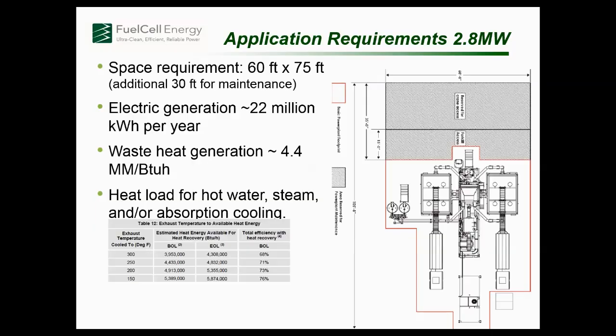For a population of about 400,000, we can put in a 1.4 megawatt fuel cell, and for a population of about 800,000, we can put in a 2.8 megawatt fuel cell. So if you've got a population of say 1.6 million, then about two 2.8 megawatt units, or 5.6 megawatts, would be the size we'd recommend. You can see below what we need on the fuel quality, and like I said, we put in our own fuel cleanup skid to make sure we're attaining that.